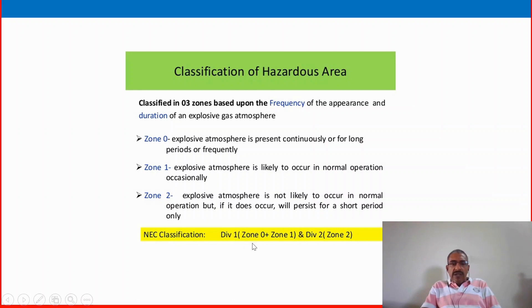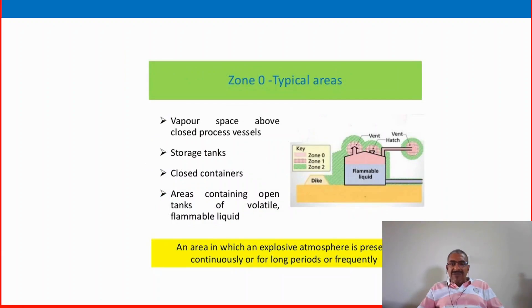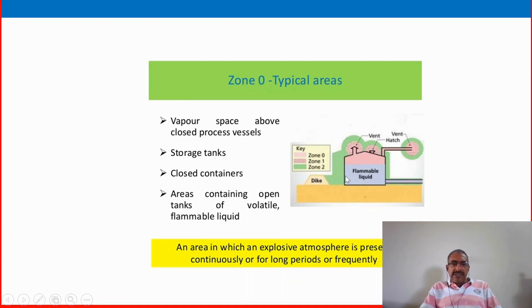The NEC classification gives Division 1 as Zone 0 plus Zone 1, and Division 2 as Zone 2. Zone 0 is defined as: vapor space above a closed process vessel, areas around vent hatches and vent lines, areas with flammable liquid storage tanks, closed containers, and areas containing open tanks of volatile flammable liquid — any area where an explosive atmosphere is present continuously for long periods or frequently. Zone 0 is very, very hazardous, dangerous and flammable.